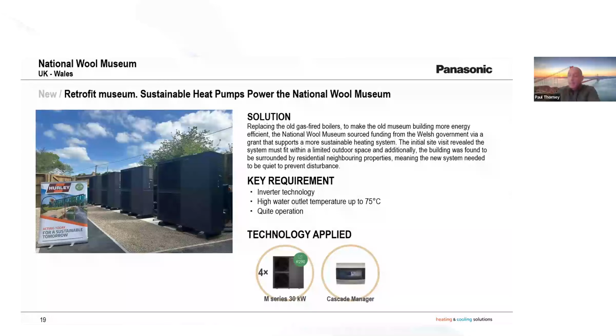This project had 4 30-kilowatt units, all hooked up with Modbus. The aim was to replace all the gas appliances at the National Wool Museum. This was done by a local installer, F.E. Hurley's, and my part was to support with the commissioning and make sure it was installed to manufacturer's instructions, which it was.